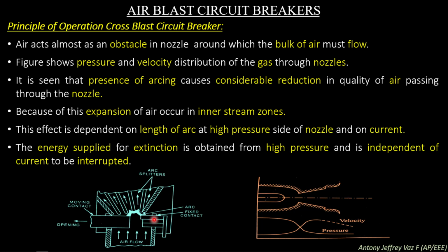The only disadvantage of the air blast circuit breaker is that we need to connect an air reservoir tank which should be supplied at a very high pressure, so we need to run a compressor to compress the air to a high pressure. More than 15 atmospheric pressure should be present inside the air reservoir tank.